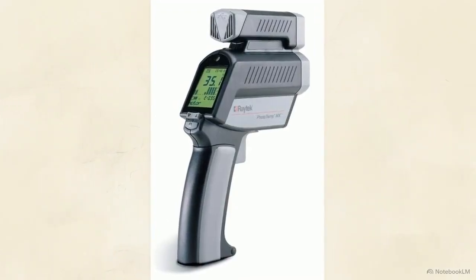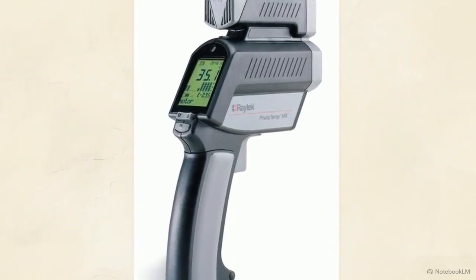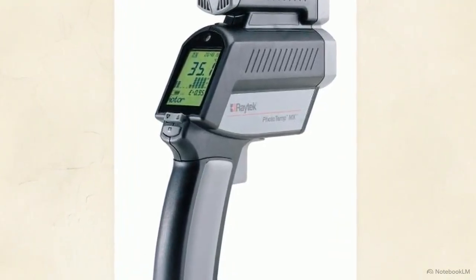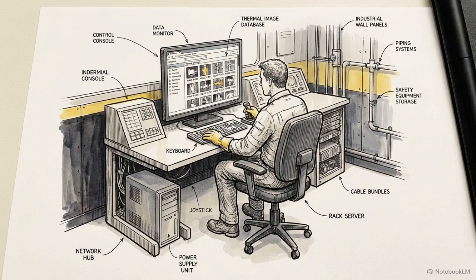To address this gap between raw measurement and contextual proof, engineers developed the Raytek PhotoTemp MX6. By integrating a digital camera directly into a precision infrared pyrometer, it established a simultaneous workflow: measure the temperature, photograph the specific target area, and document the resulting data as a single combined digital asset. Predictive maintenance requires verified visual databases to function properly. If a technician cannot locate the exact component that triggered a high temperature alarm, the recorded data cannot be accurately translated into an actionable repair order.